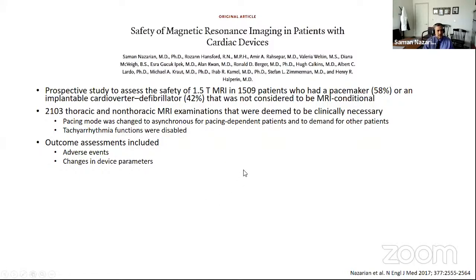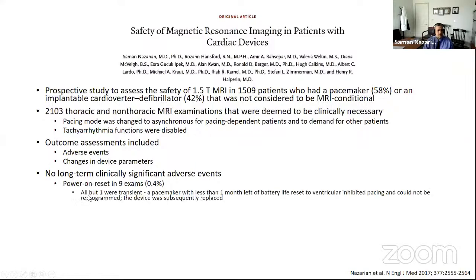And we looked at their adverse events and outcomes, and essentially we really didn't have anything clinically significant, either long-term or short-term, with the exception of one event that I'll tell you about in the short term. So long-term, no significant clinically adverse events. Short-term, we had 9 exams where we had a power on reset. This is something that tends to happen in older devices, and also when the devices are approaching ERI. So I used to say, as they're approaching ERI, let's just do the scan, because if we're going to damage it, we're going to be replacing the device soon. But the problem with that is they tend to be more likely to have power on reset.